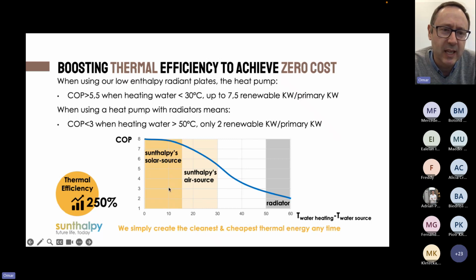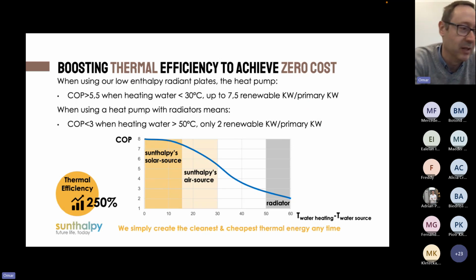As we said, if you work with a radiator, the temperature differential is high and you're going to get a low performance. If you're working with an air source, depending on whether it's a traditional air source heat pump or a water system with a fan coil, you will get performances clearly above 5, 6. And if you manage to have higher quality, higher enthalpy sources like solar, as we will see, the performance can just rocket.